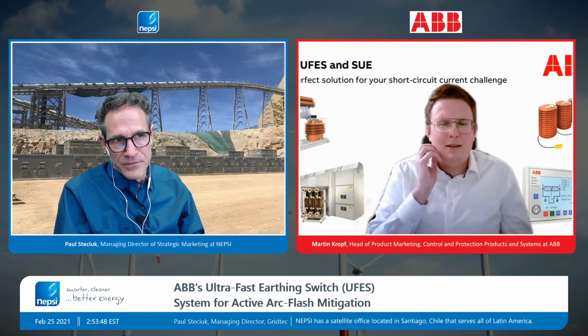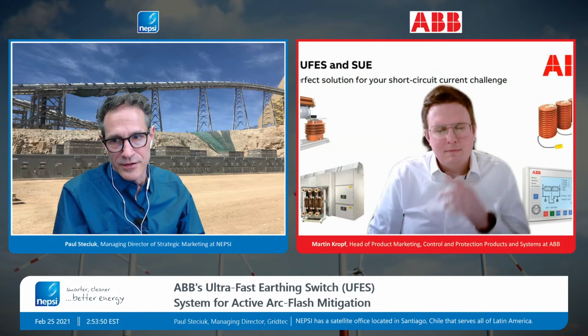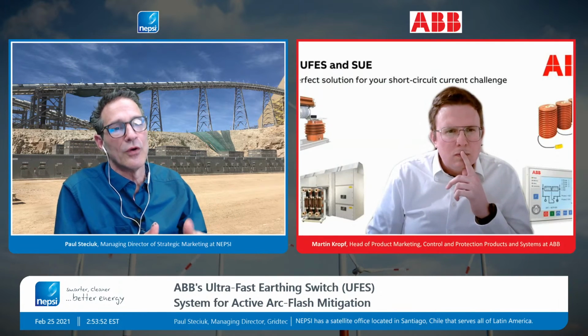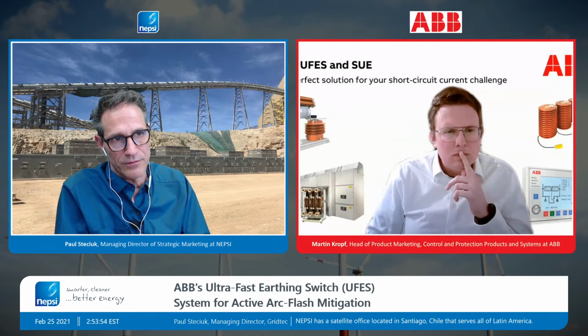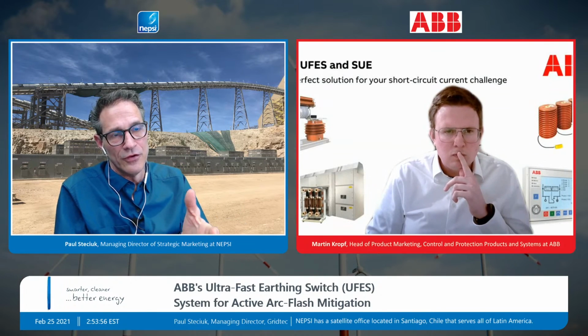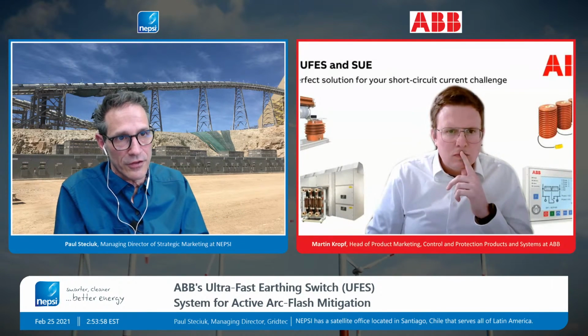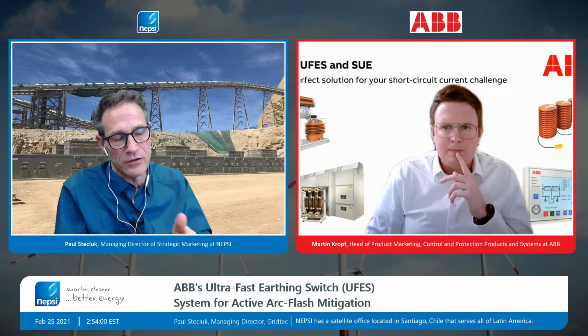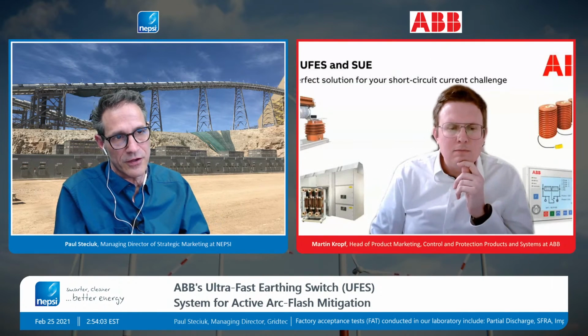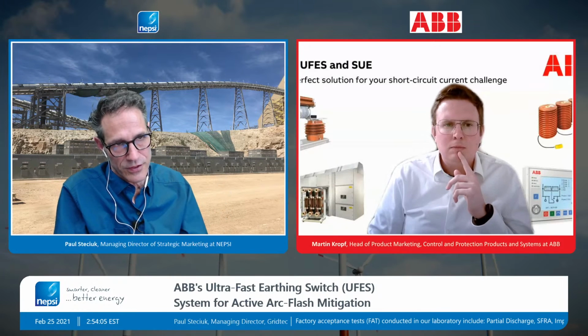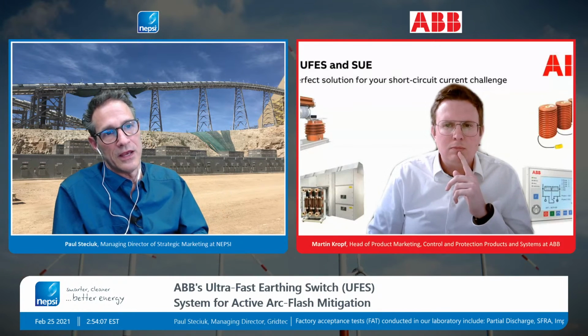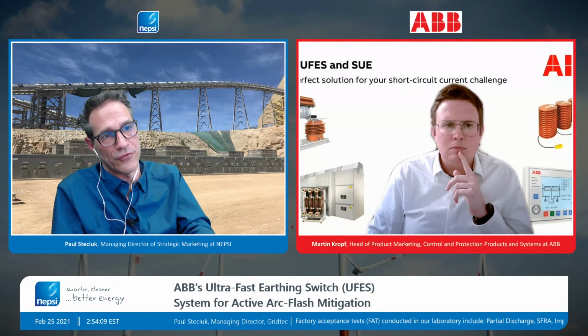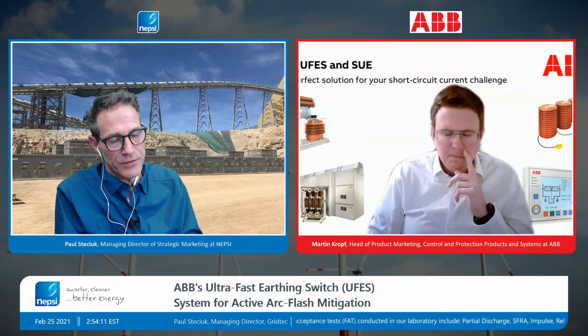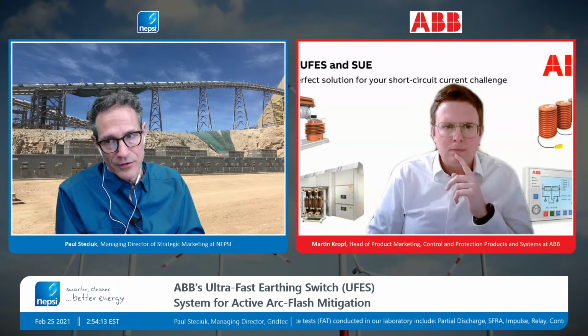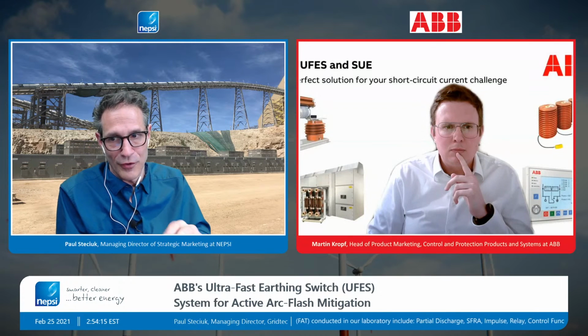Not entirely. So the question is, the UFES system ultimately requires an upstream breaker to clear, because the UFES system is creating a three-phase bolted fault. You have an arcing fault condition. The UFES system picks it up within 4 milliseconds. It shorts out that arc, right? And then it relies upon an upstream system to clear. So I think I'll answer the question, Martin, if you don't mind.